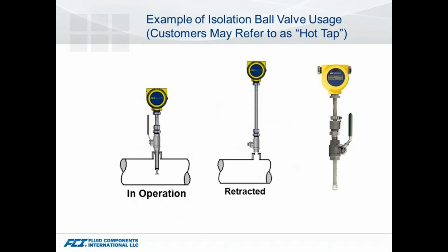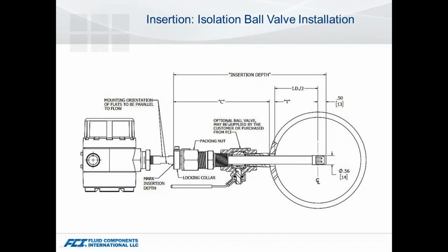Another area to consider is when you look at going with a hot tap, isolation ball valve type arrangement. So again, you can do some preventative maintenance without shutting down the process. You've really got to go in and take into account that additional length of the ball valve, how it's being installed, whether it's flanged, whether you have a 2-inch nipple on the pipe or a 4-inch nipple on the pipe. We really need to take into account those dimensions when coming up with the right insertion length. So we're at the center line plus 1/2 inch, 1/4 inch, depending upon the product.